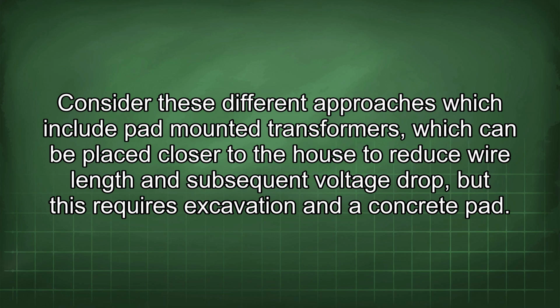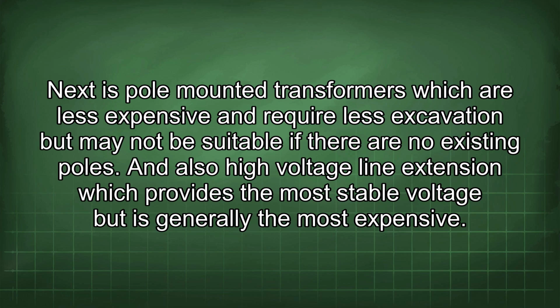Consider these different approaches, which include pad-mounted transformers, which can be placed closer to the house to reduce wire length and subsequent voltage drop, but this requires excavation and a concrete pad. Next is pole-mounted transformers, which are less expensive and require less excavation, but may not be suitable if there are no existing poles. And also high-voltage line extension, which provides the most stable voltage but is generally the most expensive.